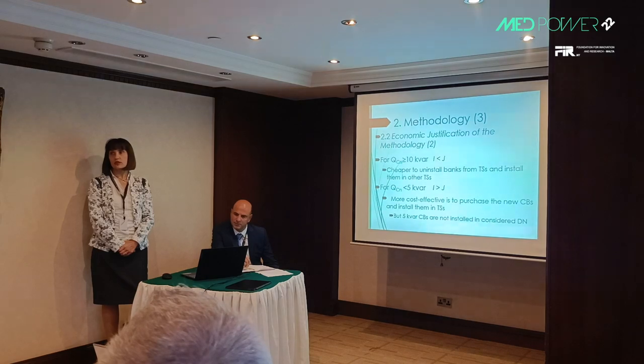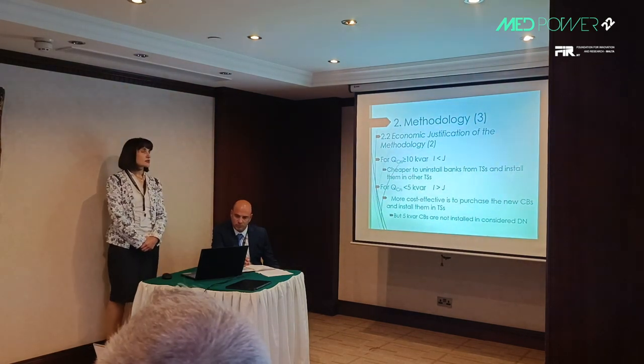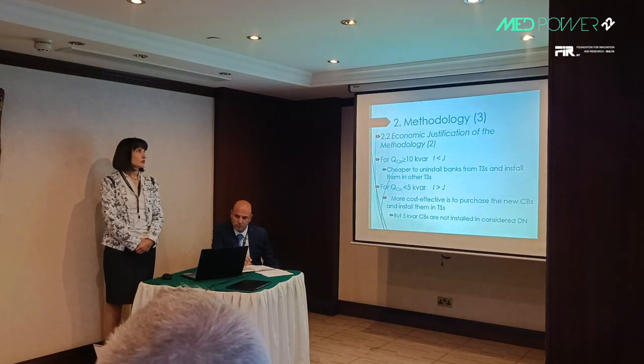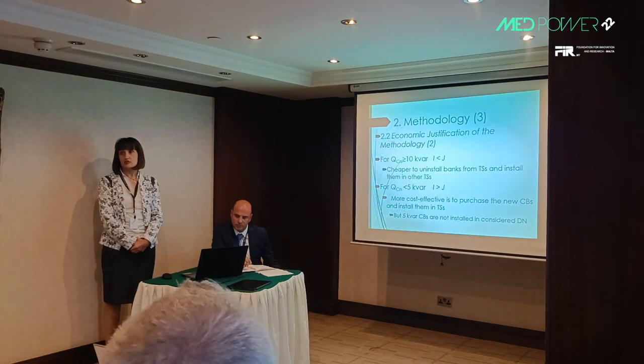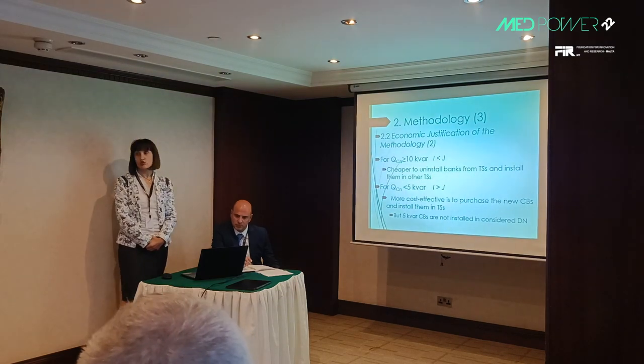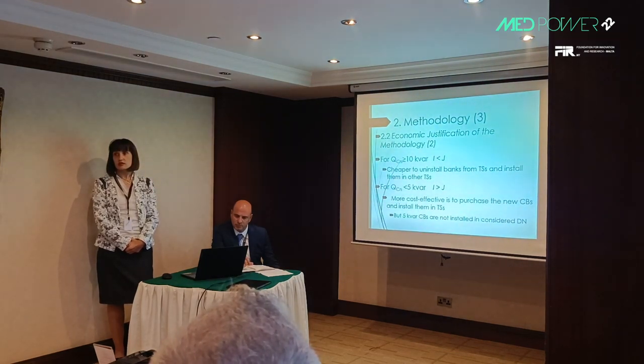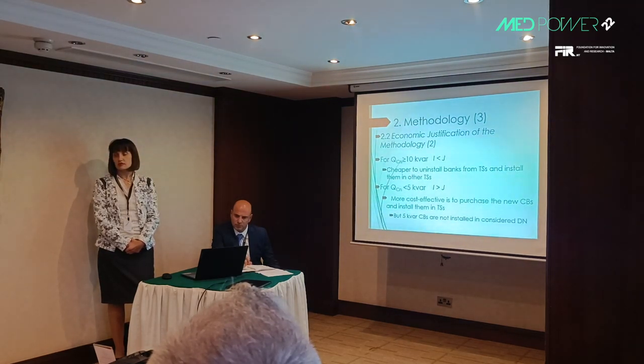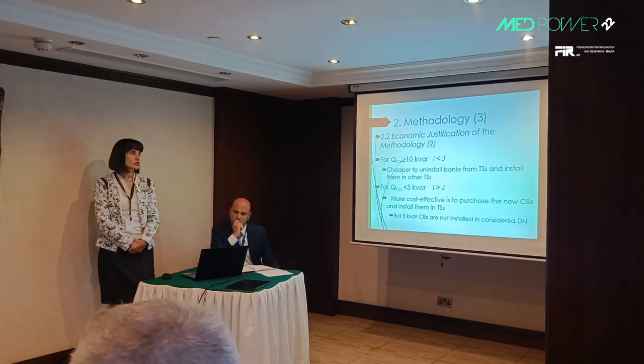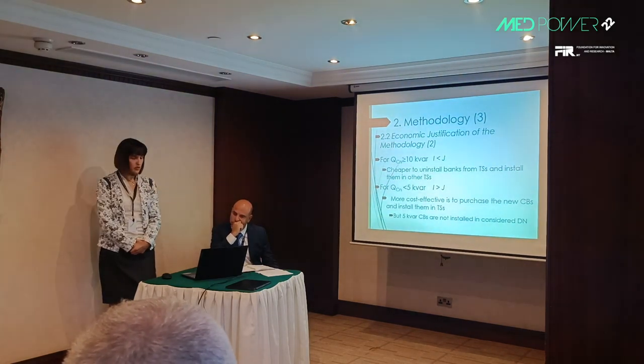It is calculated that in the case of capacitor banks with a rated power greater than or equal to 10 kvar, if the uninstallation cost i is less than installation cost j, it is cheaper to remove capacitor banks from overcompensated substations and install them in substations where insufficient compensation is noticed. For capacitor banks with rated power less than 5 kvar, these are not the subject of this paper, as the examined distribution network does not use such capacitor banks.